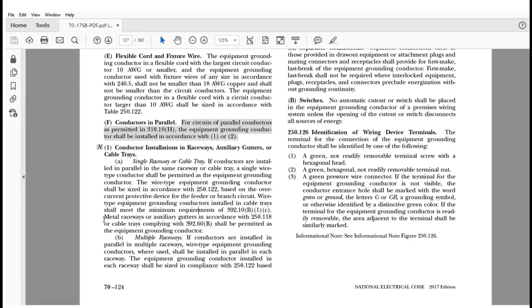Now it says metal raceways or auxiliary gutters in accordance with 250.118. That is where they qualify as an equipment grounding conductor in themselves. Or even a cable tray that might qualify in its construction and in its listing in accordance with 392.60(B) shall be permitted as the equipment grounding conductor. So it's not prohibiting you from running a wire type equipment grounding conductor, and many engineers do encourage it.